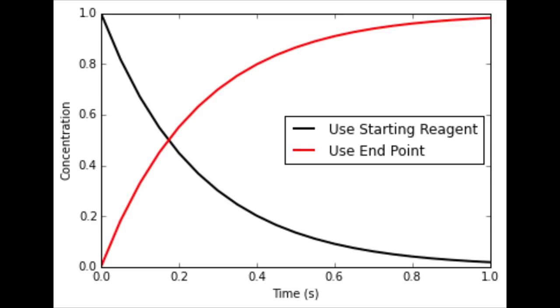In general, if we expect the fluorescent signal to increase over time, it is sensible to set the high voltage with the cell containing the reaction endpoint. If we expect the signal to decrease, we typically set the high voltage with the cell containing the fluorescent reagent along with either buffer or water.